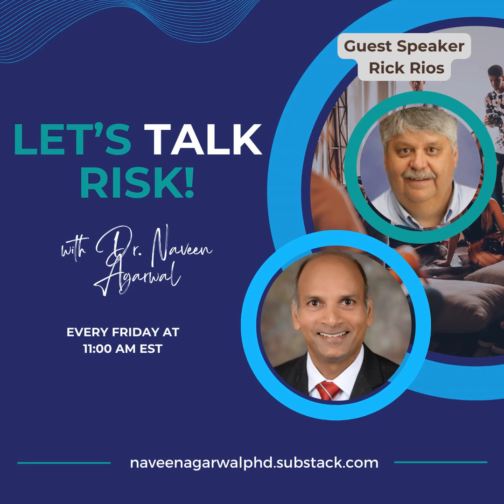So you're talking about the risk management process. What I'm hearing you say is that in the purpose, we would expect to see why we are doing risk management in the first place. What's the design intent of risk management? Right. And so then you have to go to 14971 and read the first 2 pages, the foreword and the introduction. You have to figure out in the first 2 or 3 pages what the design intent is from that standard, and you can use that and word it to your benefit in your procedures.